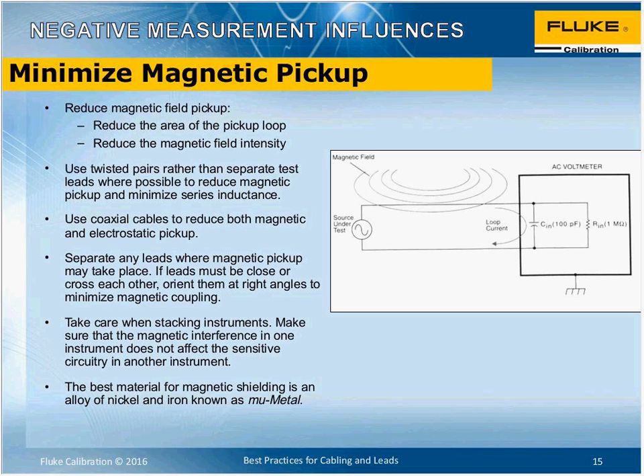If you stack instruments on top of each other, you may actually be bringing into close proximity a radiation source inside an instrument with a sensitive circuit inside another one. The typical example is a mains transformer, a line frequency 50-60 hertz transformer, which is radiating, and if it's not particularly well shielded, it will radiate through the instrument case into another instrument. So be careful when you stack instruments on top of each other. Those kinds of things can happen. You might want to put them by the side or move them around. You can easily see when something is going on because you can see an effect, so just take a minute or two to think about it and perhaps reorient the instrumentation and see if you have a problem.